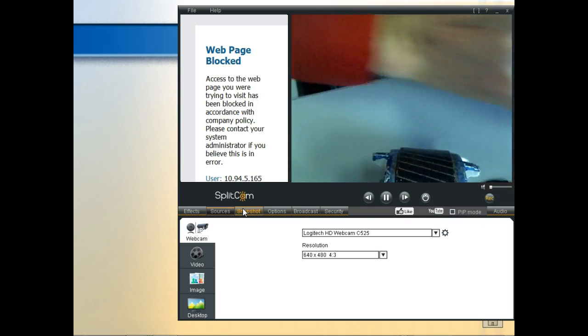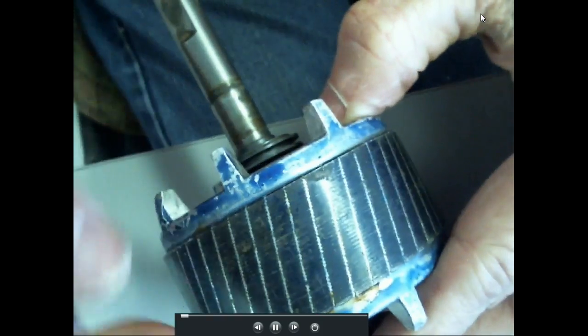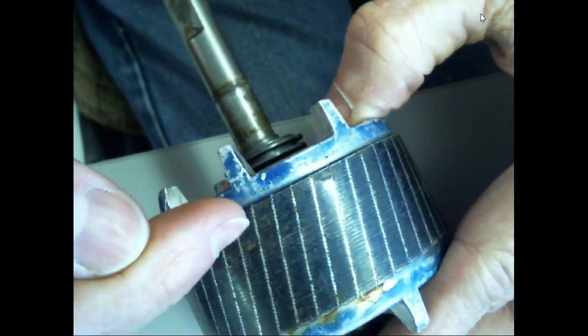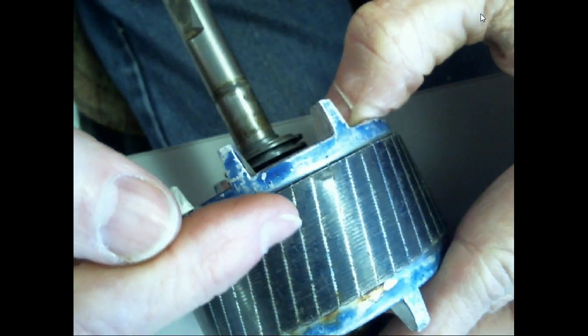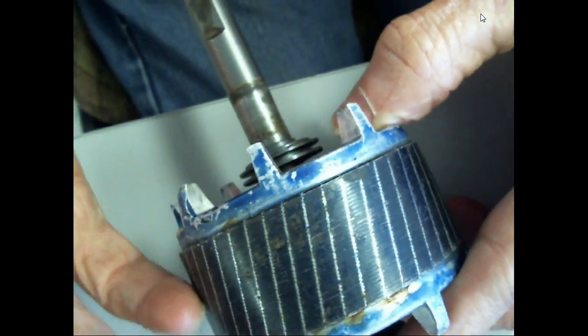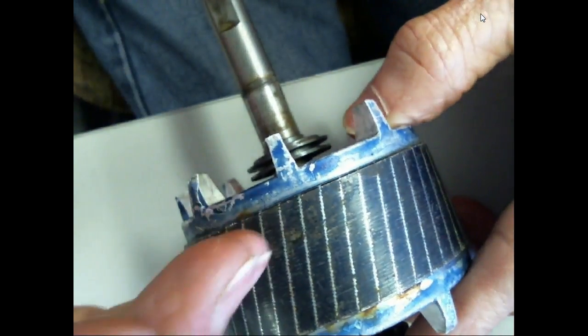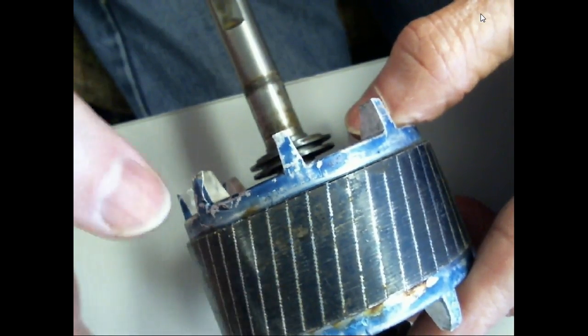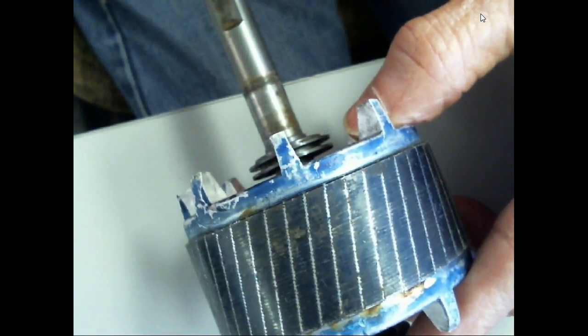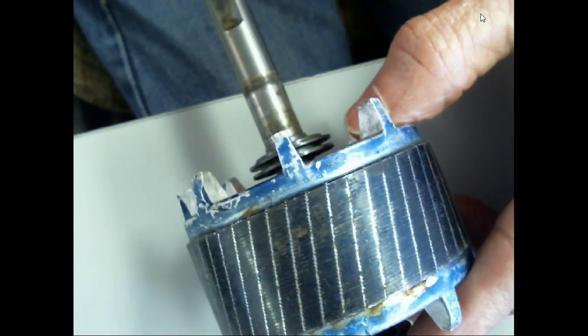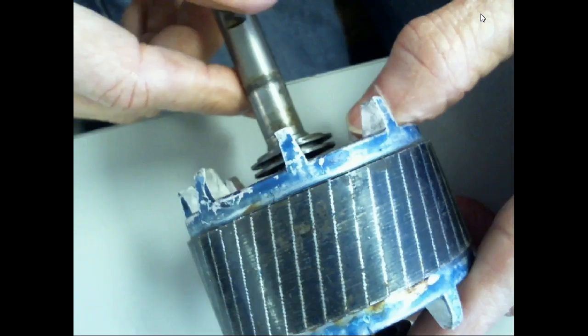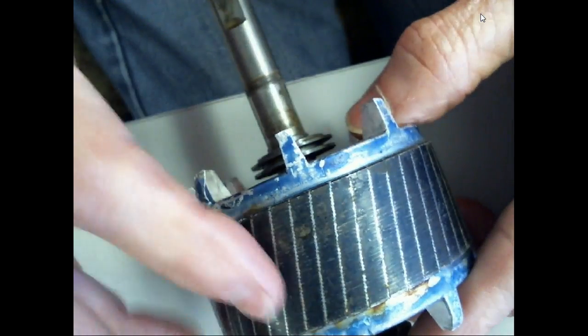We've got conductors inside that we're inducing voltage into, but we want to concentrate the magnetic field. I'll pass this around so you can see it shows up well on video - see all the little plates divided up, the little slashes? That's what we call laminated plates. A lamination is just a thin, coated plate placed between each plate, and it prevents the current in one piece of metal from adding to the next. So anything dealing with AC where we're trying to concentrate a magnetic field will use laminated plates like this.